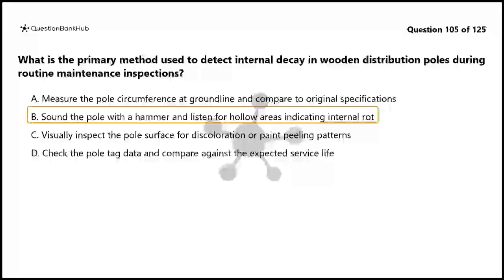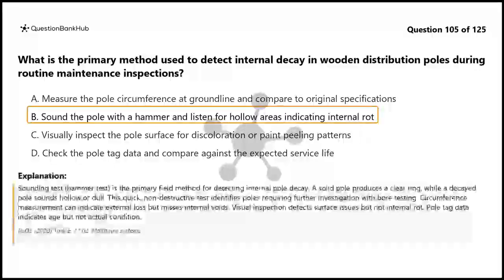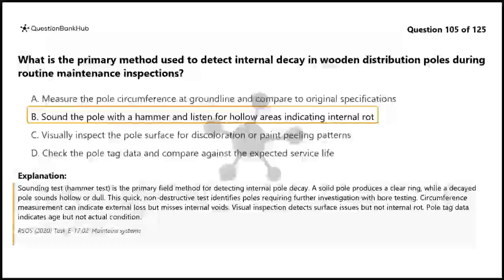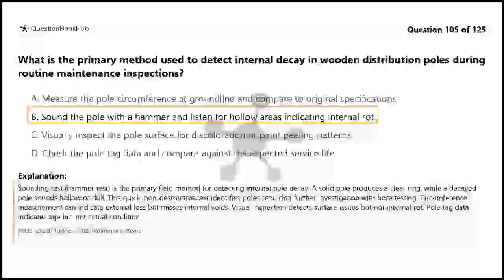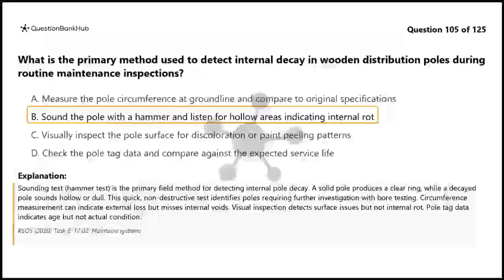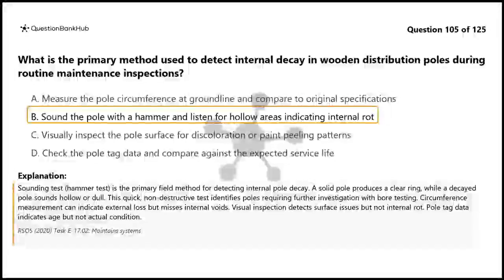The correct answer is B. Sounding test, hammer test, is the primary field method for detecting internal pole decay. A solid pole produces a clear ring, while a decayed pole sounds hollow or dull. This quick, non-destructive test identifies poles requiring further investigation with bore testing. Circumference measurement can indicate external loss but misses internal voids. Visual inspection detects surface issues but not internal rot. Pole tag data indicates age but not actual condition.